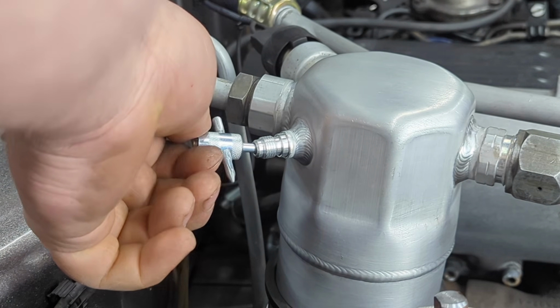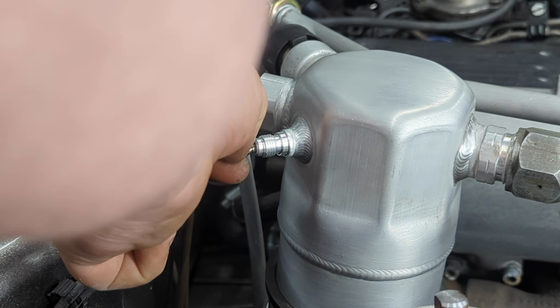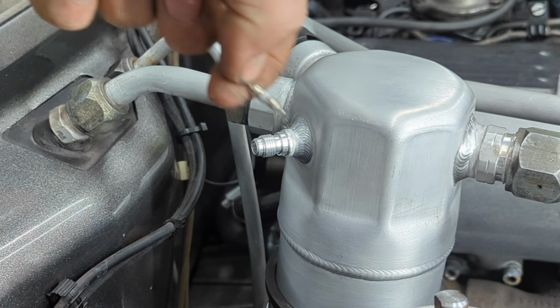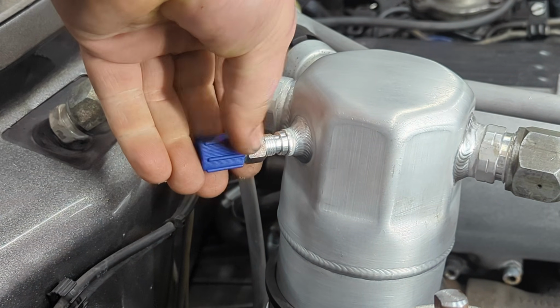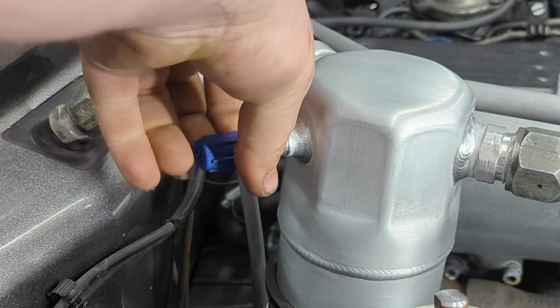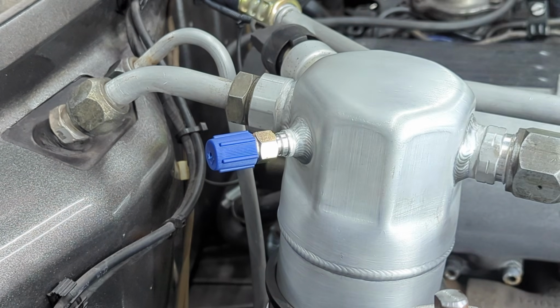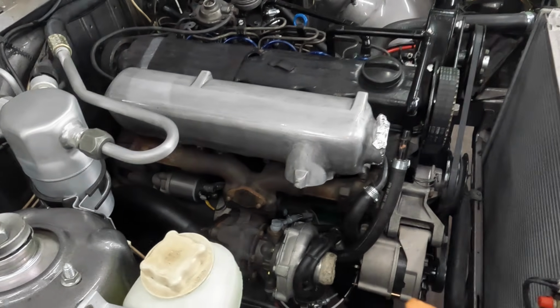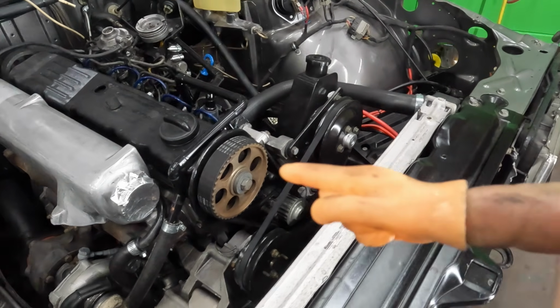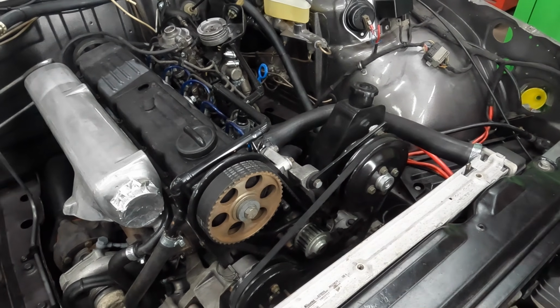So for this style of valve, you just unscrew the existing Schrader valve and then thread the adapter right onto that service port. Depending on what flavor you have, you might not have to take the Schrader valve out, but just read the box. And with that taken care of, the only thing that has to be opened on the system again is the compressor, so I can put the oil in. Now, a word on oil.